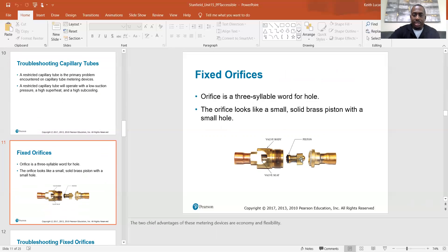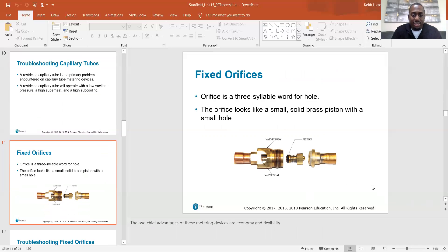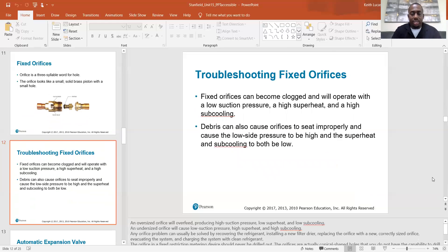The fixed orifice — or piston — is a tiny little orifice with a small conical hole that restricts refrigerant and drops the pressure at the outlet. The two chief advantages are economy and flexibility — meaning they're cheap and easy to install. Fixed orifices can become clogged and will operate with low suction pressure, high superheat, and high subcooling. Debris can also cause orifices to seat improperly, resulting in high low-side pressure with both superheat and subcooling being low.